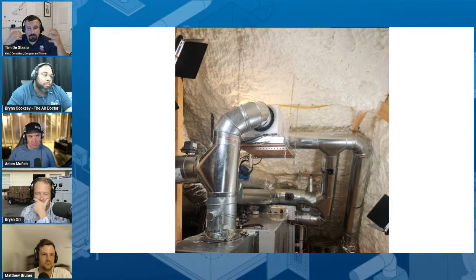Well, after doing a bunch of research and reading from a lot of building science people, you come to understand that especially open cell spray foam is a little bit vapor permeable. So it absorbs vapor. And then your roof structural stuff starts absorbing moisture. And it happens at night. And then during the day, when the sun comes out, the sun heats up the roof and it drives all that moisture out. But that moisture is buoyant, and so it just kind of hangs out at the ridge.